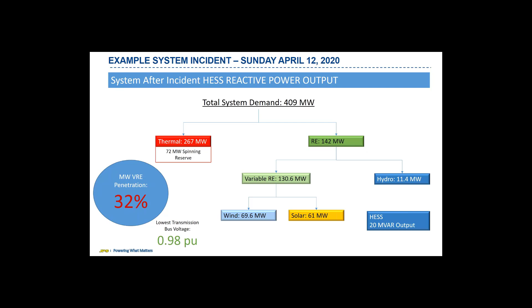So operators now use the storage to give us about 20 megavars of reactive support. This is the system immediately after the storage was used, brought into play very quickly. The system parameters are more or less the same, the megawatt penetration of VRE is still at 32%, and demand is still around 409 megawatts. But now with this additional reactive power support, we're able to increase the lowest transmission bus voltage up to 0.98. This is not perfect, but it's within tolerance, and definitely a better position than before.